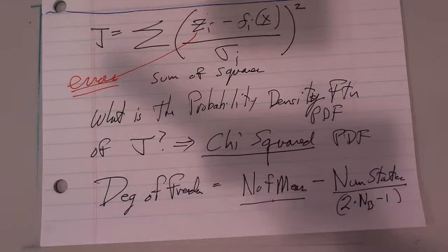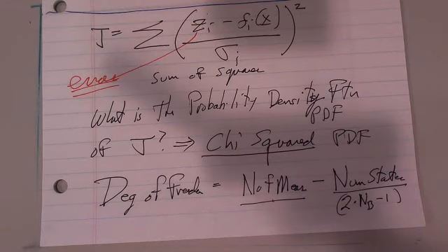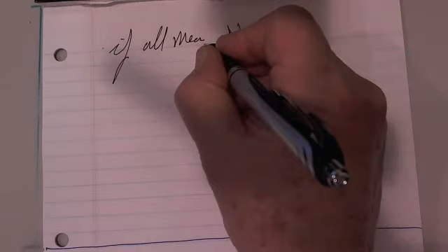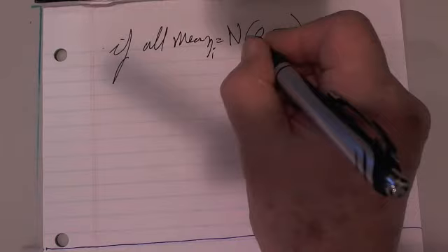What we'd like to know then is, if we get a chi-squared distribution, I can tell you what the mean of the chi-squared distribution is. It has to do with the degrees of freedom. If the value of J comes out very different from that mean, really way off, then the chances are that I've got a bad measurement.